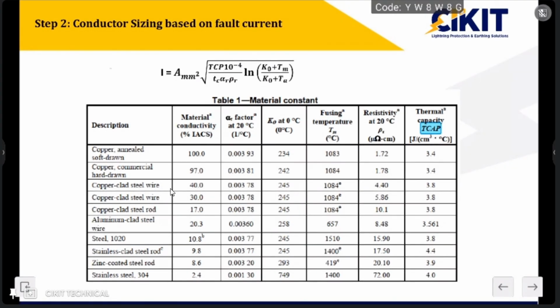The second step is conductor sizing. As I mentioned, the primary purpose of providing earthing is to dissipate the fault current. If we are dissipating the fault current, the conductor should be able to withstand it. If it is able to withstand, then only it can dissipate. So the standard has provided the formula for calculating the current carrying capacity of these conductors. If you closely observe, the current carrying capacity mainly depends upon the cross-sectional area, the thermal capacity and different parameters. One of the parameters is the resistivity, and another one is the time, that is the clearing time. So the time is one of the important parameters when we are calculating this current carrying capacity.